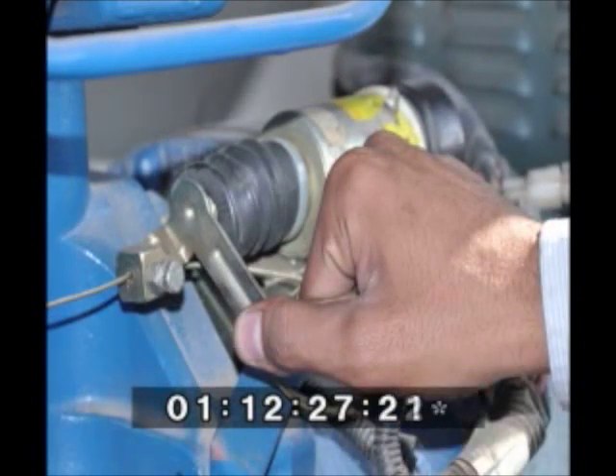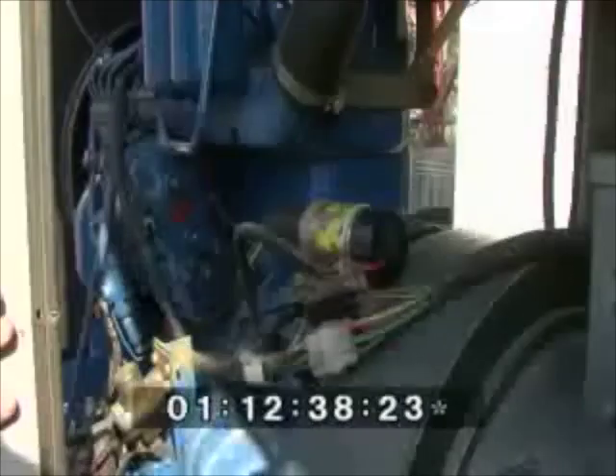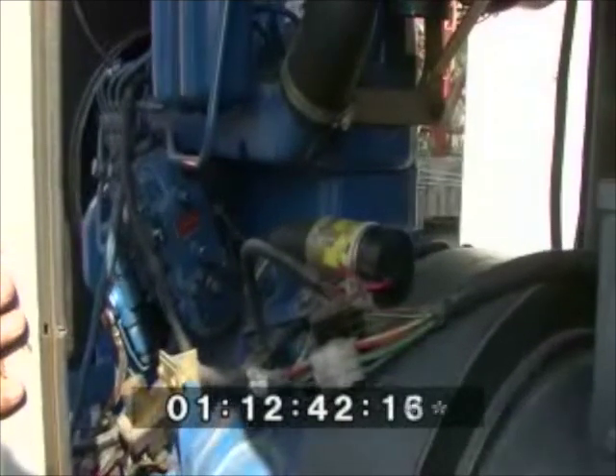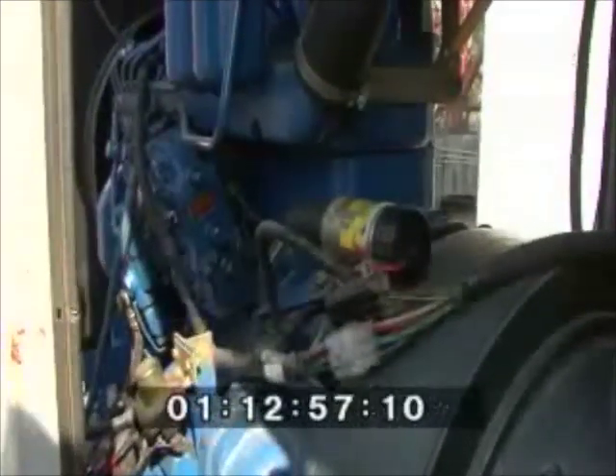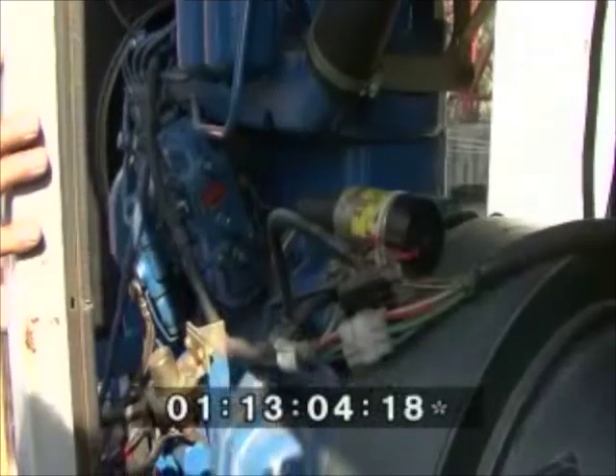Now we have come to the back of the canopy. We will see where the stop solenoid switch is placed and how it works. You can see the stop solenoid switch. This switch is responsible to stop the DG in auto mode. In case of power failure, the DG starts working. When the power is restored, the DG is stopped by the solenoid switch. We can also use the stop solenoid switch to stop the DG when it is running in manual mode.